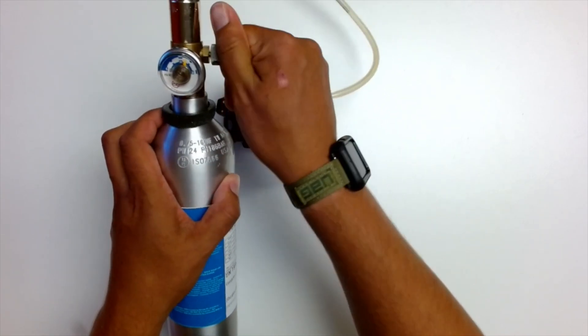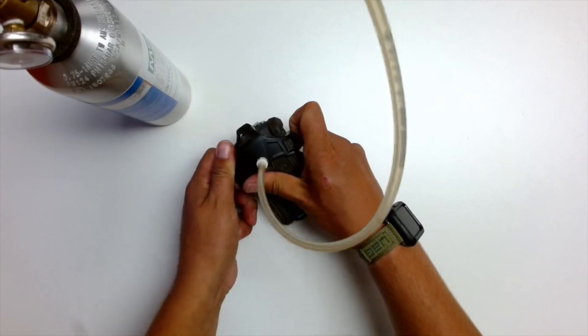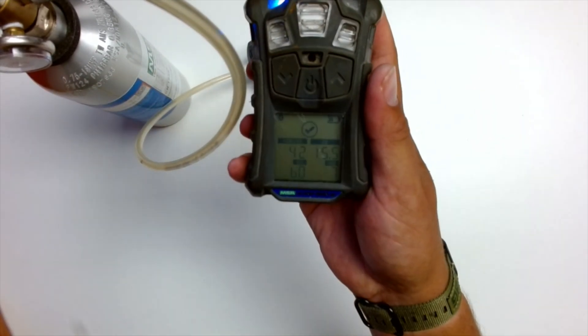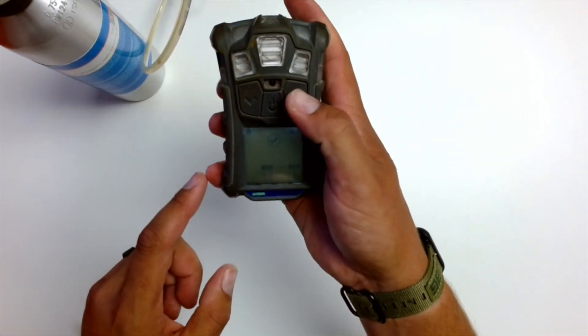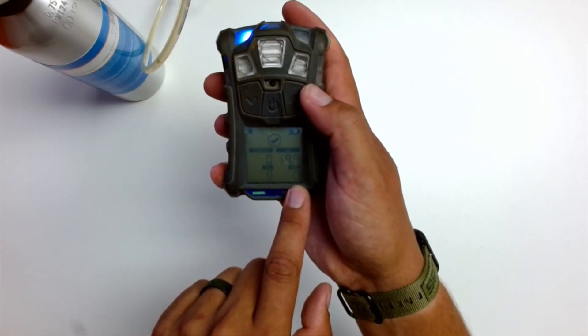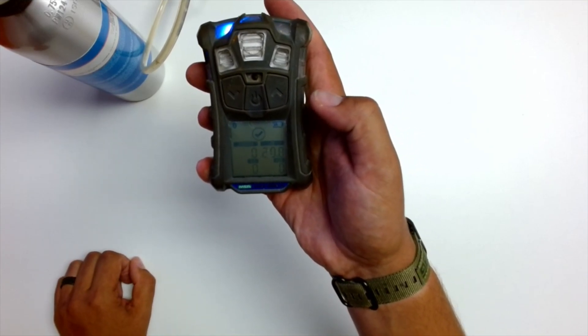And then what we're going to do is turn our fixed flow regulator back off, remove our face clip, and you'll see the values should start to come back down here now. These three are going to hit zero, and then your O2 sensor should come back to 20.8.